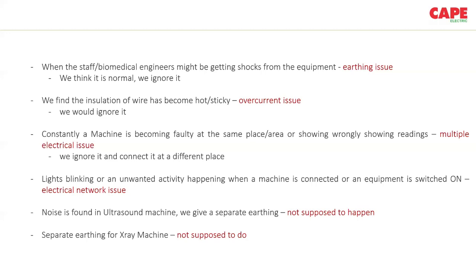The next thing that we find is that we might find some insulation of the wire. It tends to be sticky or hot at some point of time. So what happens is that it might be due to an overcurrent issue. We should not ignore it. We should not just leave it just like that. We have to check the electrical connection there.